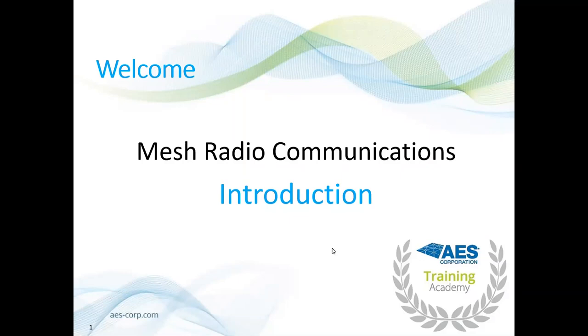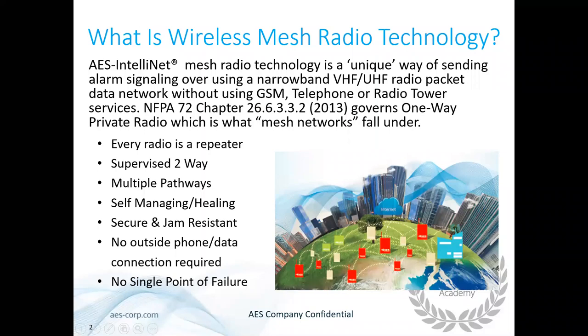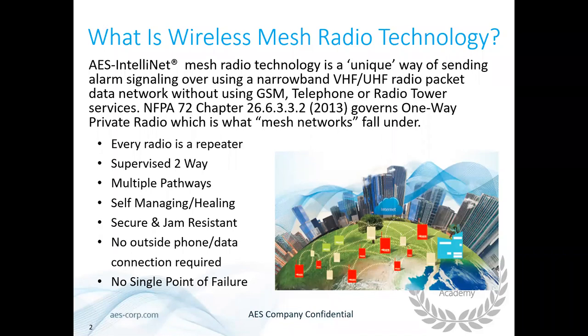Thank you everybody for taking the time to join us to talk about mesh radio. I've been working with AES doing training for the last couple years, and one of the most misunderstood portions of working with this technology is antenna selection. First, I want to go over mesh radio technology. It's a unique way of sending alarm signals using narrow band VHF or UHF radio packet data. We fall under NFPA 72 Chapter 26.6.3.3.2 — the 2013 version — which governs all one-way private radio, and this is what mesh networks fall under.